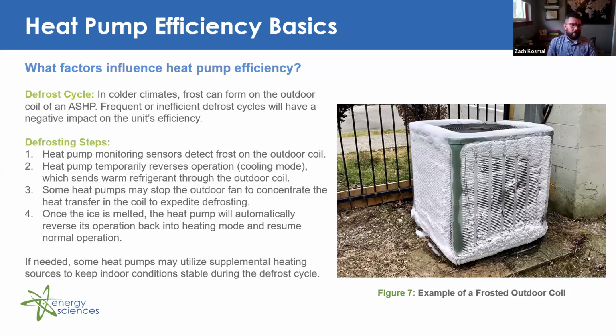So it should be noted that heat pumps are typically designed to operate with a longer cycle time than a typical traditional HVAC system. With that said, if an oversized heat pump is installed, then it'll likely operate on shorter cycle times. This will allow for the occurrence of frosting on that outdoor coil more frequently, so you kind of want to avoid that. In addition, short cycling causes excessive wear and tear on components, especially in heat pumps. Things like the compressor will bang on and off repeatedly, which is just not good for the equipment.